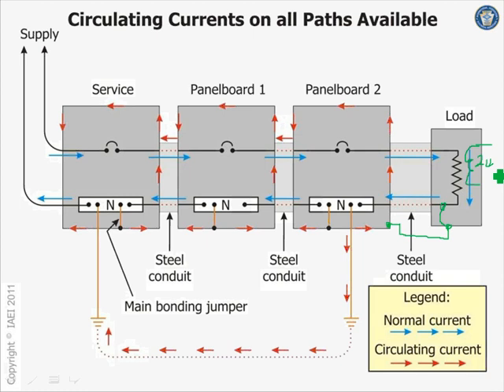Yeah, you have to isolate the whole equipment from ground, which is really weird to think about, but we have to do that because a lot of the electronics are tying the neutral to ground inside some of these pieces of equipment. That's legit in the NEC code book, and it's still safe. The code allows you to take one isolated ground all the way up to here. That isolated ground is at the load level, not in the electrical panel. Most of the equipment is plugged in, and you're tying your equipment to the isolated ground, as well as your rack. Nothing wrong with that. Then you eliminate the circulating current.